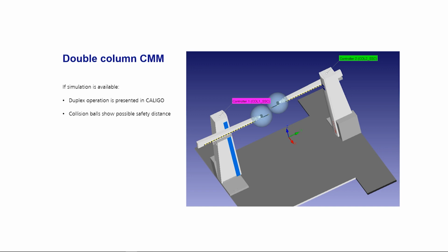This protection is switched off by default though. In the simulation, I can show you this very easy. The collision protection is given in head coordinates, is measured from head to head, and is freely definable according to your wishes. Anyway, the distance should be at least so big that the two reference probes cannot get in each other's way. What is important? Nevertheless, the measuring areas of the two columns can overlap. They just can't approach beyond the range of the protective sphere.